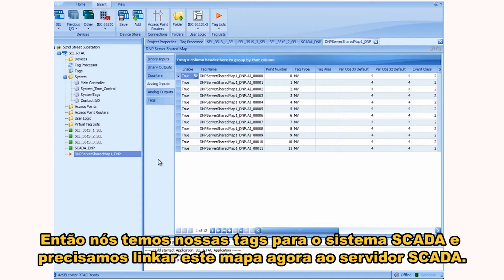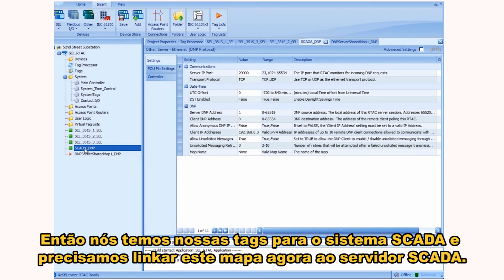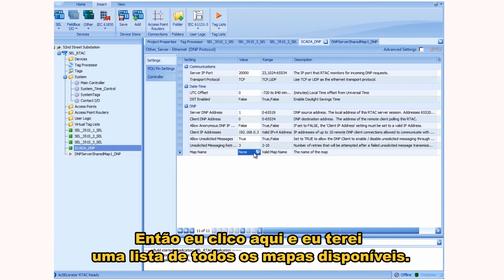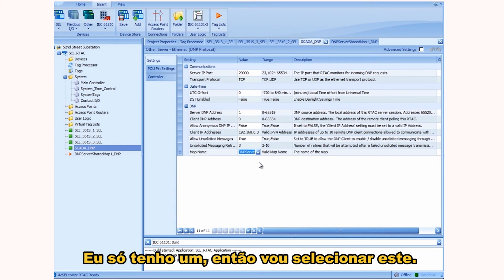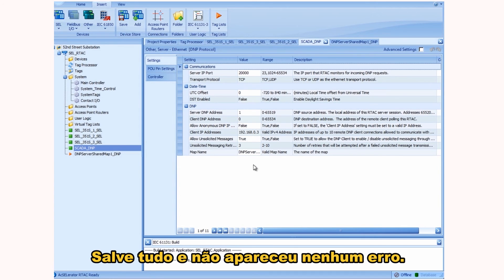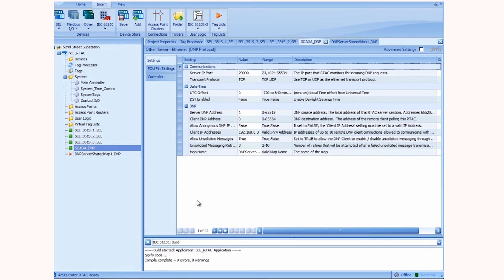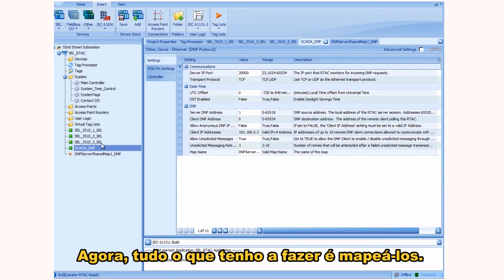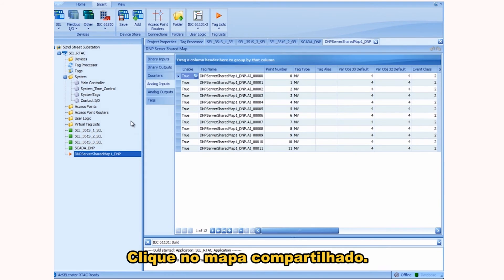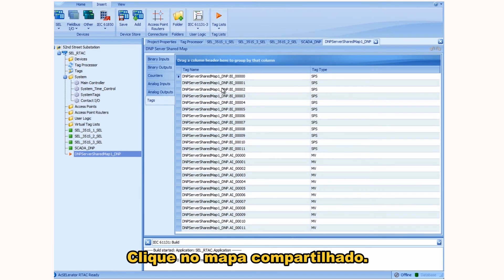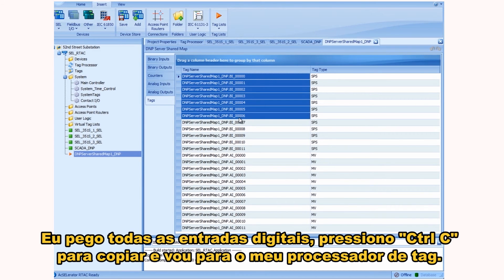Now we have our tags for the SCADA system, and we need to link this map to our SCADA server. I click on the server and it gives me a list of all available maps. I just have one, so I select it, save it all, and no errors appear — errors would show up at the bottom. Now I click on the shared map and grab all of the binary inputs.